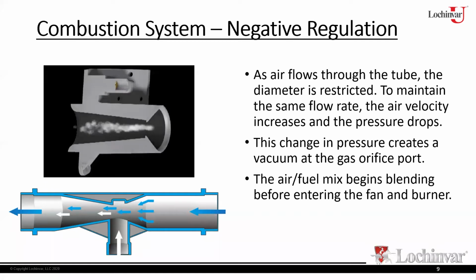All right, so as airflow goes through the venturi, we basically create a vacuum at the gas orifice. The stronger the vacuum on the gas orifice means we have a stronger vacuum on the valve itself, which causes the diaphragm in the valve to move. All right, so the more suction we put on the diaphragm, the higher the diaphragm lifts, the more gas flows out of the valve. So basically it's all airflow. So the more air you move through the venturi, the more gas you're going to pull through the valve. So as the fan ramps up, more gas flows. As the fan ramps down, less gas flows. Anything that affects our airflow affects our gas flow in a neg reg system.